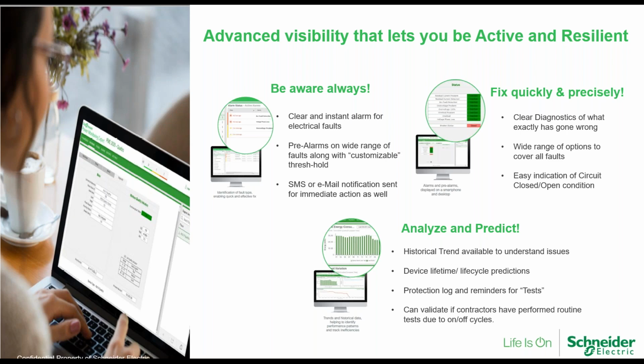So this allows you to always be aware. You get clear and instant alarms for electrical faults, but better, more than the alarm on the electrical fault, is the pre-alarm. It's a pre-alarm on a wide range of faults that has customizable thresholds. So you could, for example, program the system and say, if the circuit hits a load threshold of 60%, send me an alarm. The circuit might not have tripped, or the circuit might not have switched off, but at this point, there's a potential risk and we need to get to site to fix this problem.